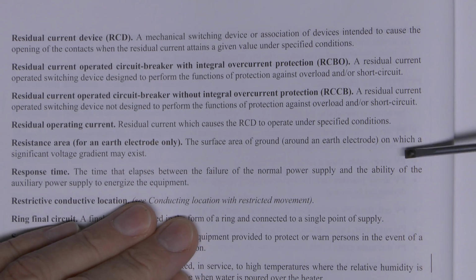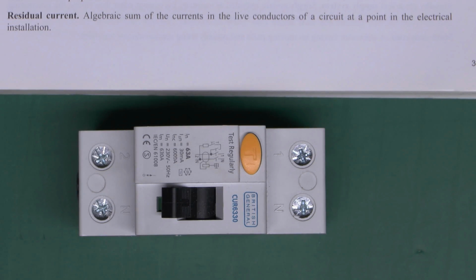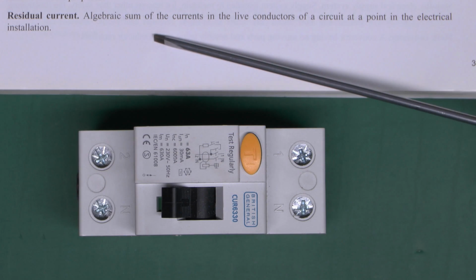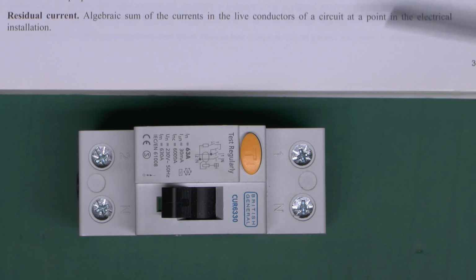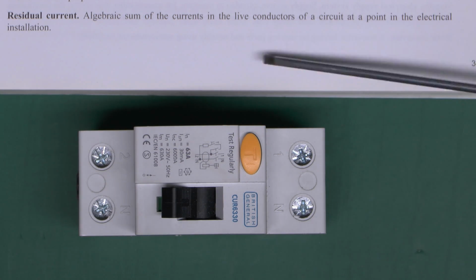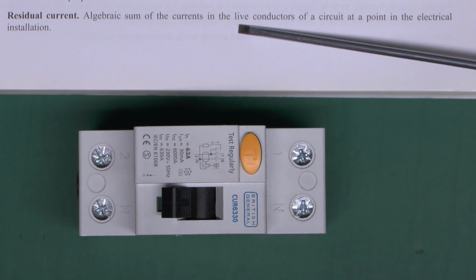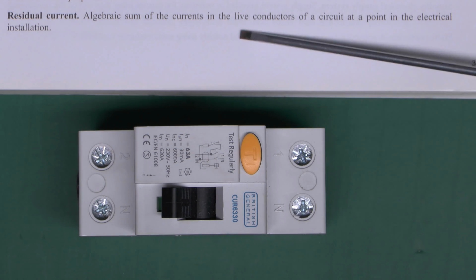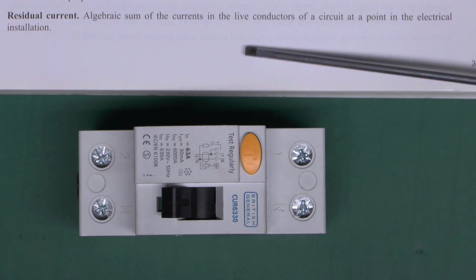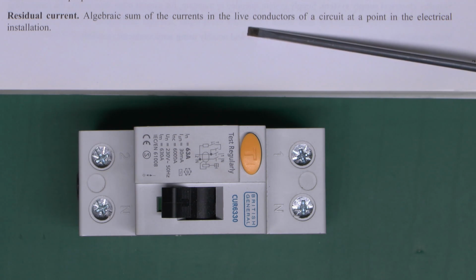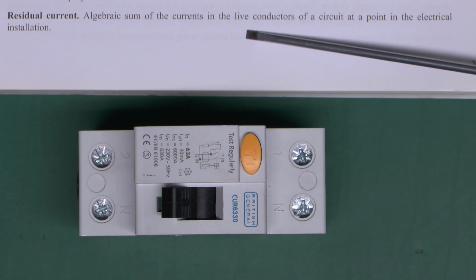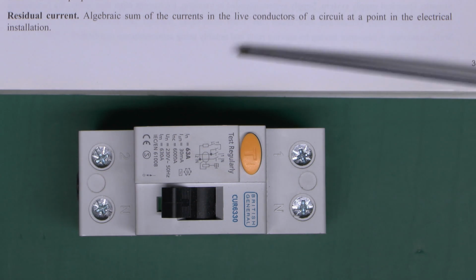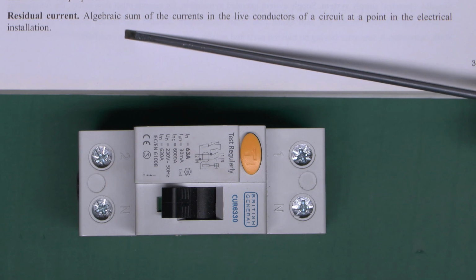Now, residual current is a fairly odd term, but nevertheless we'll see what that one actually is defined as. That's on the previous page. Now, residual current is defined here as the algebraic sum of the currents in the live conductors of a circuit at a point in the electrical installation. Now, in this case, live conductors refers to both the line and neutral conductors, because those are both live conductors. Notice the difference between live and line. Unfortunately, a lot of people call the line conductor live, but that's another story. And algebraic sum, of course, is simply adding the two currents together.